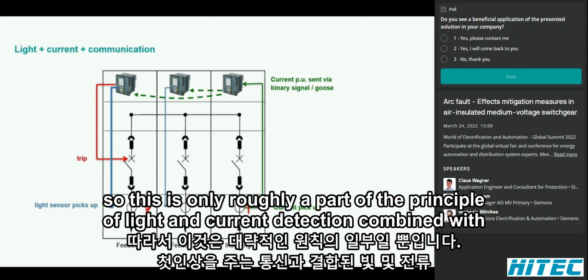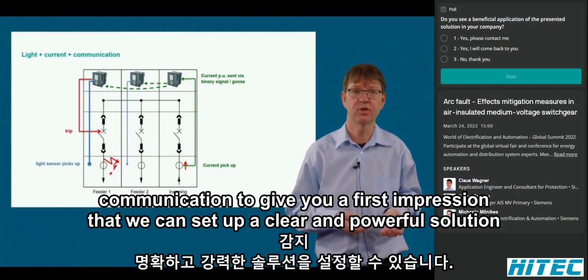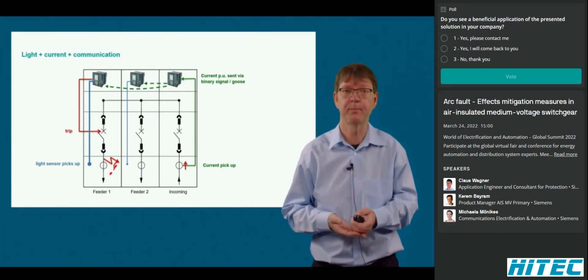It is mandatory to evaluate the current in the in-feed because faults in the local cable compartment, which are upstream the current transformer, as indicated, are not seen by this current transformer. So this is only roughly a part of the principle of light and current detection combined with communication to give you a first impression that we can set up a clear and powerful solution.